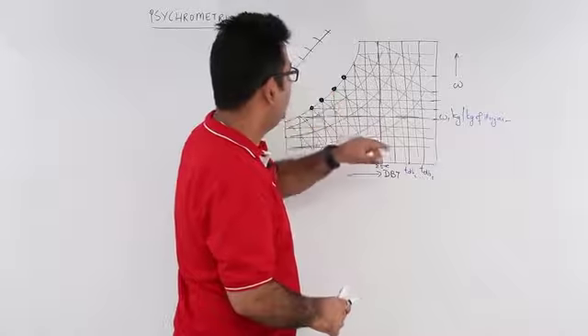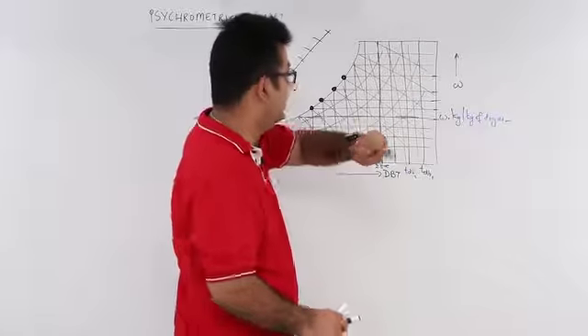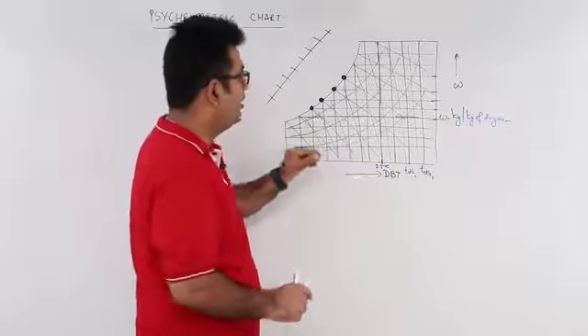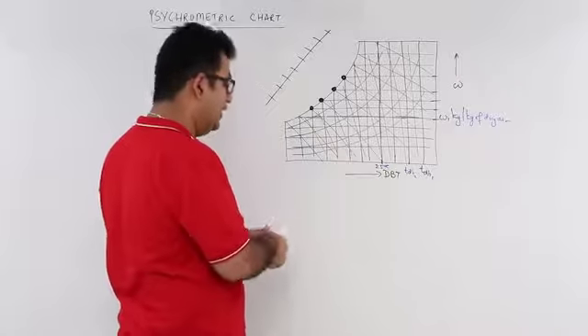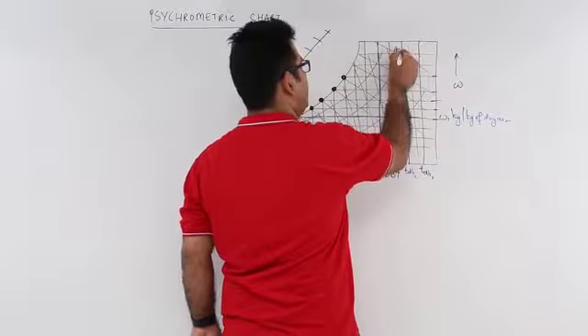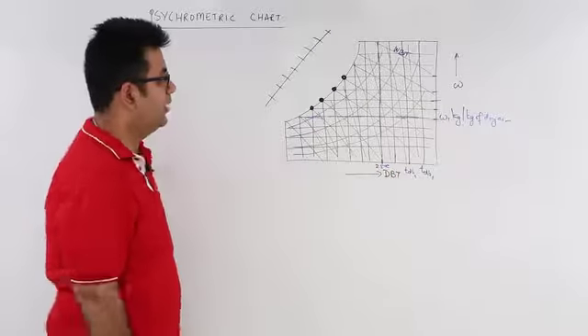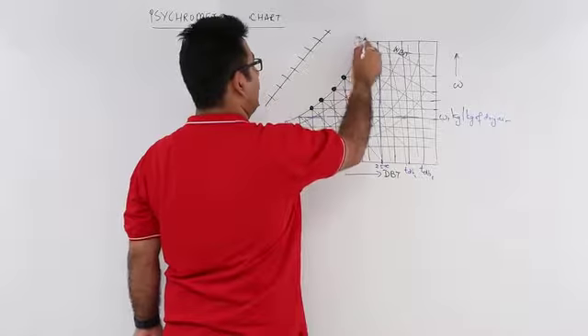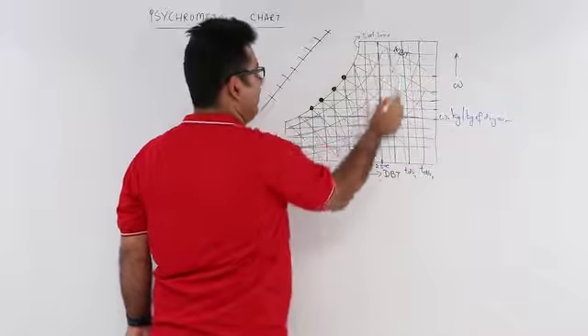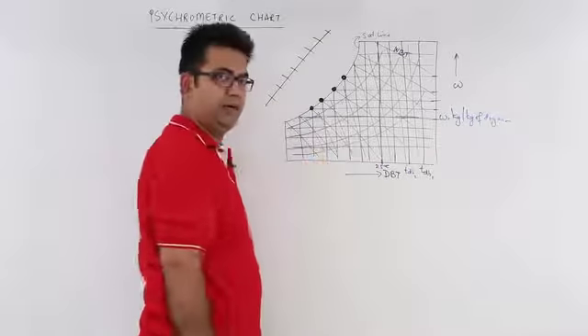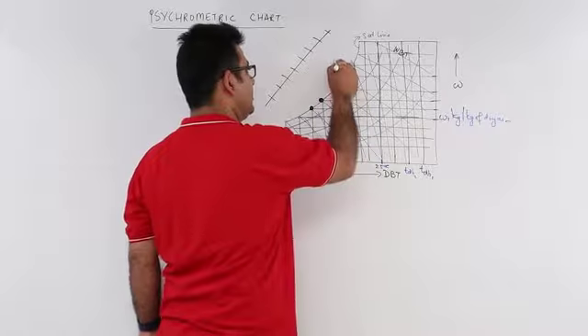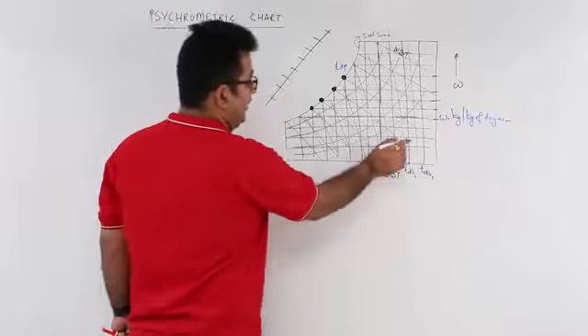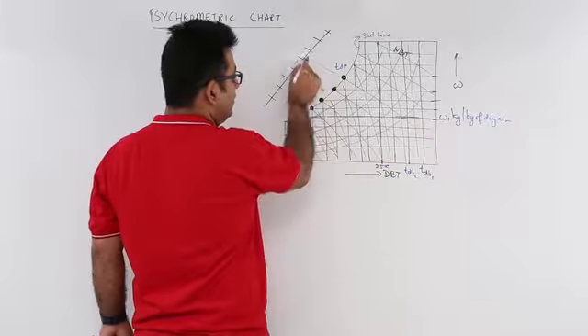Now there are two kinds of slant lines: the black colored ones and the red colored ones. The black colored slant lines indicate the wet bulb temperature. When the wet bulb temperature line meets the saturation line, that intersection point gives us the dew point temperature.